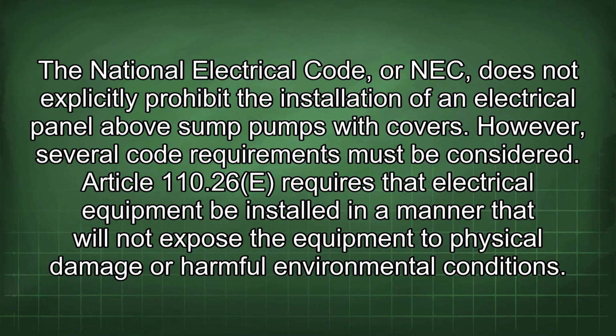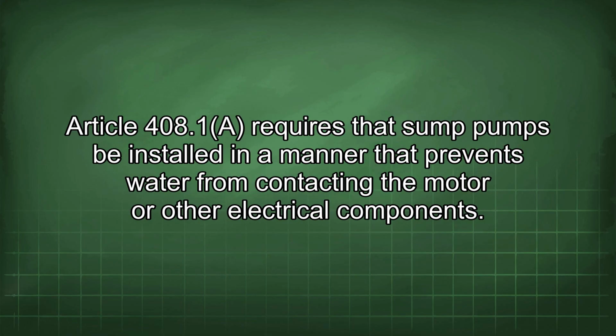The National Electrical Code, or NEC, does not explicitly prohibit the installation of an electrical panel above sump pumps with covers. However, several code requirements must be considered. Article 110.26(E) requires that electrical equipment be installed in a manner that will not expose the equipment to physical damage or harmful environmental conditions. Article 408.1 requires that sump pumps be installed in a manner that prevents water from contacting the motor or other electrical component.